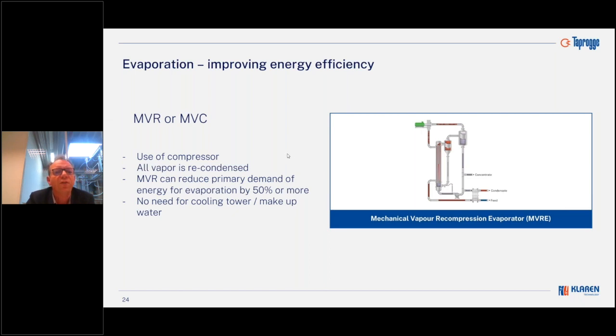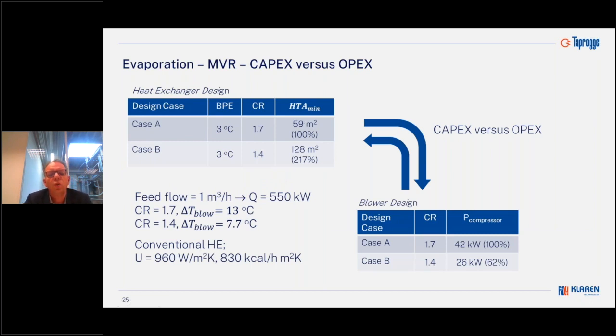But there is an important trade-off in the design of MVRs, and that's what you can see in the next slides. This has to do with the design of the heat exchanger. As I said, you use the compressor to generate an additional temperature, and this temperature you get by a certain compression ratio. The higher the compression ratio, the more temperature you get, and this also means that you can design your heat exchanger smaller. So if we take case A, this gives a compression ratio of 1.7, giving a temperature increase of 13 degrees. At the end, you would get to a heat exchanger design of almost 60 square meter.